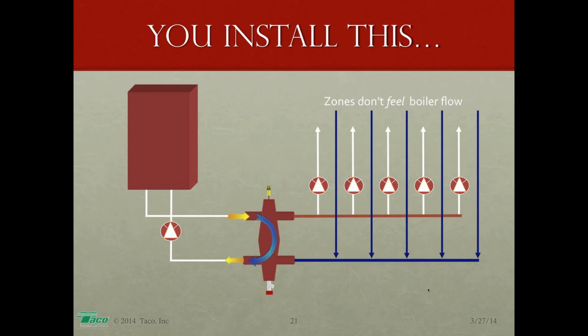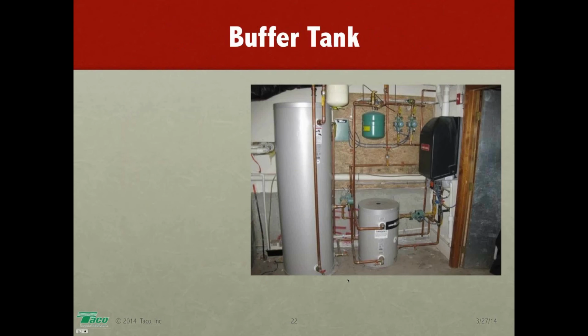So again, zones don't feel the boiler flow, and the boiler doesn't feel the zone flow, and that's the beauty of a hydraulic separator. Okay, you can either build it yourself, you've got to build a big old fat header, or you could buy it, bang it on the wall, and be done with it. All right, now let's talk about buffer tanks because a lot of questions have come up that really lead us to the buffer tank, and this should carry us right up to the top of the hour.